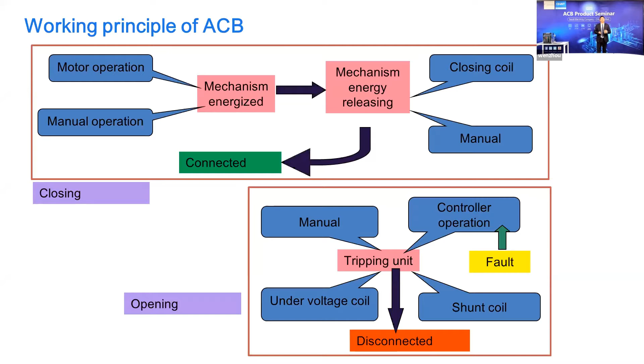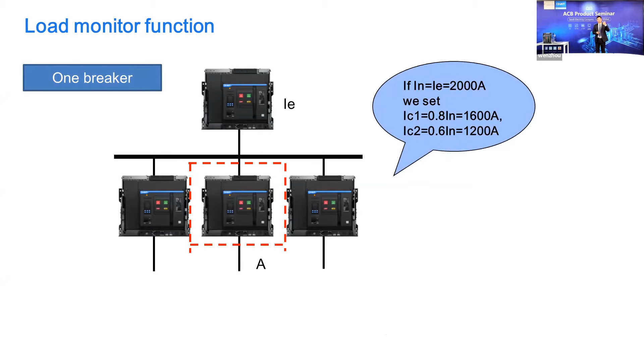Like this one, after this, for some engineers, for design engineers, I will show you for our ACB. We have a very useful function, but maybe only several persons use it. But I suggest you use it. This function is called load monitor. The load monitor we apply for our H-type and P-type ACB. Like this one, now I say I have 2,000 ampere, and we set IC1 and IC2 in the top breakers. Like this one, if the real current goes to 1.2 IC1 equals 1920 ampere, the breaker will disconnect, will shut off automatically.